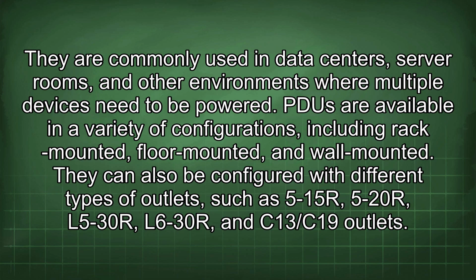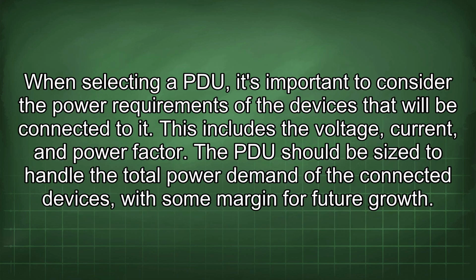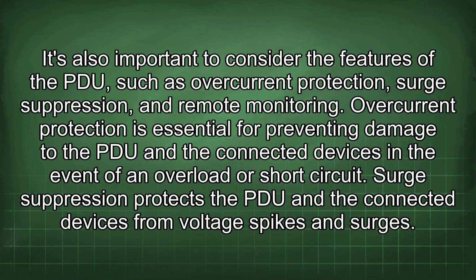They can also be configured with different types of outlets, such as 5-15R, 5-20R, L5-30R, L6-30R, and C13/C19 outlets. When selecting a PDU, it's important to consider the power requirements of the devices that will be connected to it. This includes the voltage, current, and power factor. The PDU should be sized to handle the total power demand of the connected devices, with some margin for future growth.